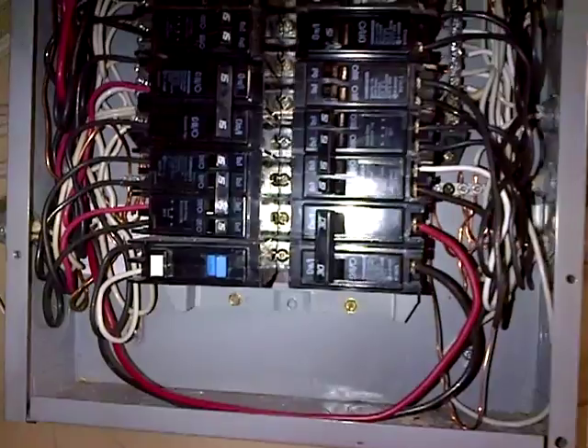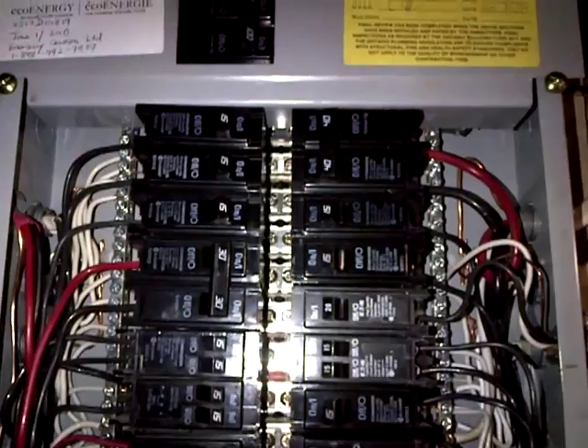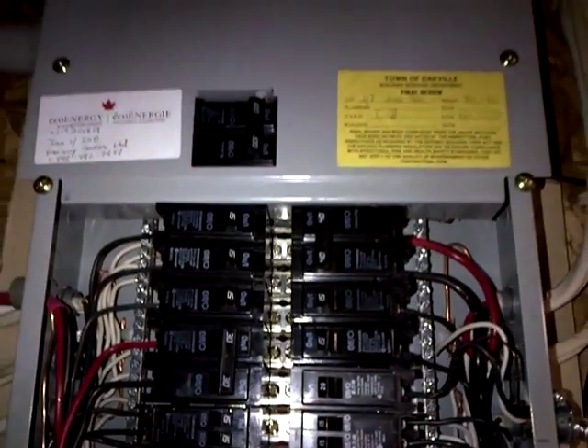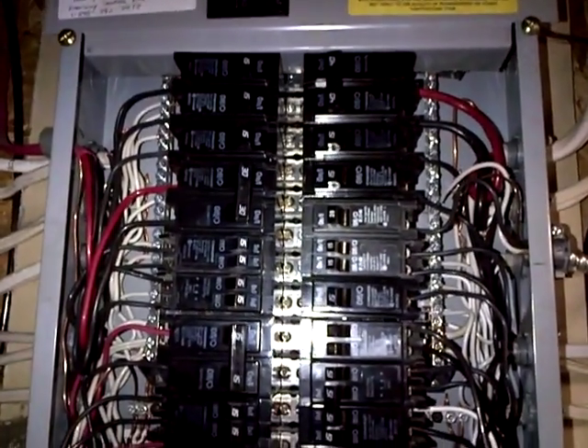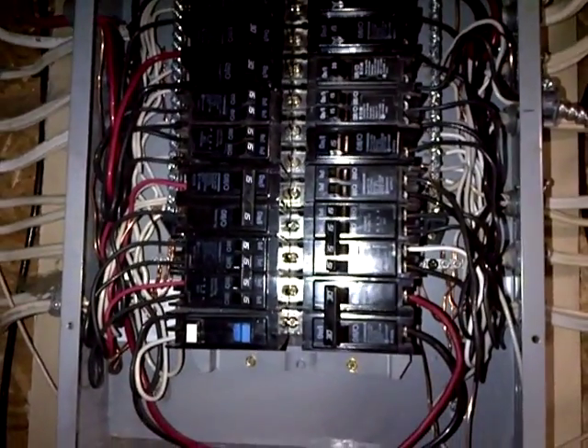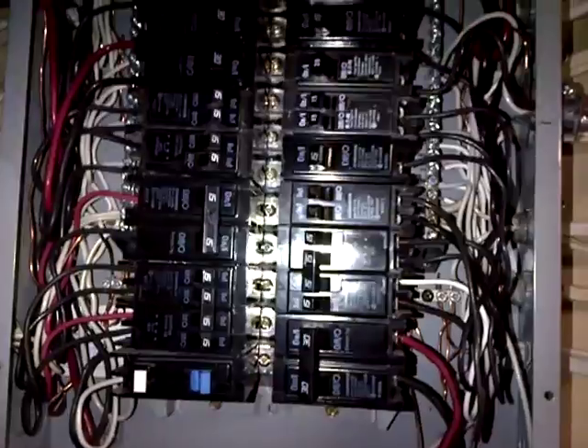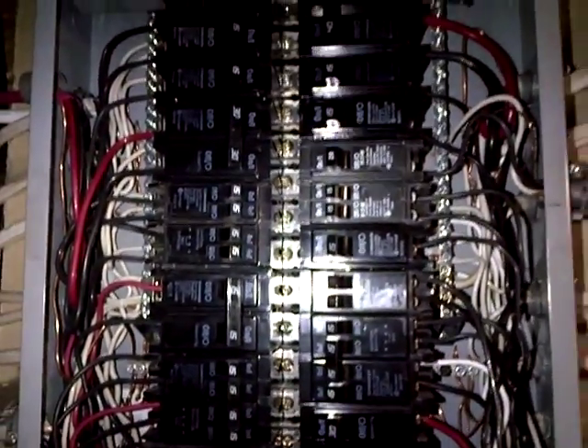I've labeled that up as well. Scanning the bus bar is something you want to do. These terminals here look very clean. This box isn't bad, but this particular model has been discontinued and replaced with just a regular push-in.